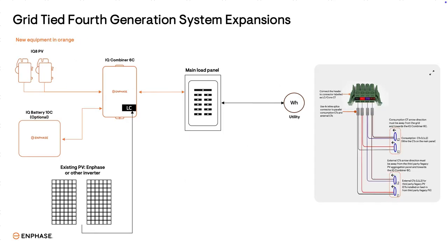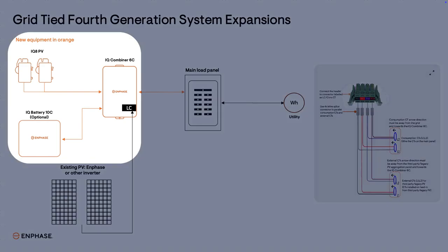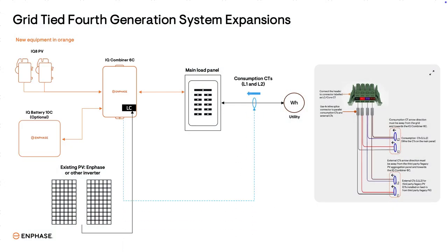Now let's take a look at a grid-tied example. In grid-tied setups, you add PV and possibly batteries as well, but the system would lack backup capability. This option may be desirable if saving more money is the only priority and backup power isn't needed. The expansion system consists of the IQ Combiner 6C, IQ 8 PV, and optionally batteries as well. Note there is no IQ meter collar in this configuration. To enable consumption monitoring, consumption CTs must be installed on L1 and L2 of the utility feeders to the main load panel, and an additional set of consumption CTs must be installed on L1 and L2 of the existing PV. The CT leads must be wired in parallel to port number 8 in the IQ Combiner 6C.